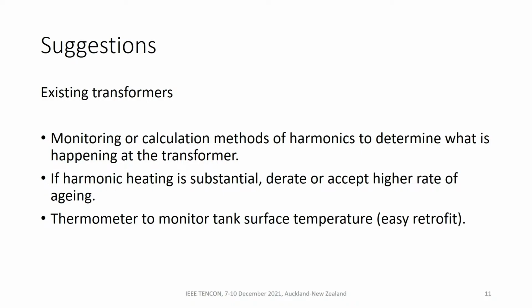Now, if we are seeing harmonic heating, then an option is to derate the transformer. So that could be one if the utility doesn't want to replace it, or wants to save some money: just derate it. Another one is just to accept the higher rate of aging. This applies if a transformer has been fairly lowly loaded over its life and the paper is in good condition. If they're only expecting 50 years of life out of it, then they might accept this higher rate of aging because the transformer will still last that long. Other things we can see here are thermometers to monitor the tank's surface temperature. What we like about this is that it's an easy retrofit.